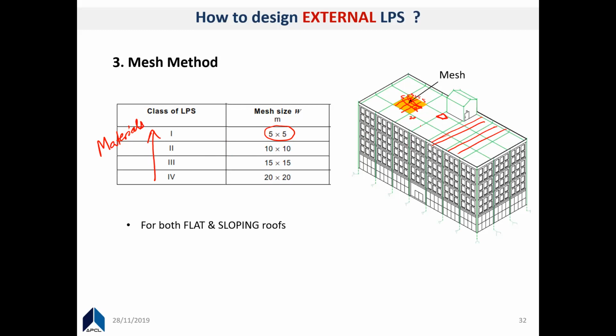So when you check this out, you can see this is a combination of air termination methods. You have a mesh and you have these air arrestors. So you have a mesh as here, you have meshes. So unless you have any other protection to be maintained, then there's actually no need of having these air terminals over here. But you have to make sure that all this is to the most edge of the structure to be protected.